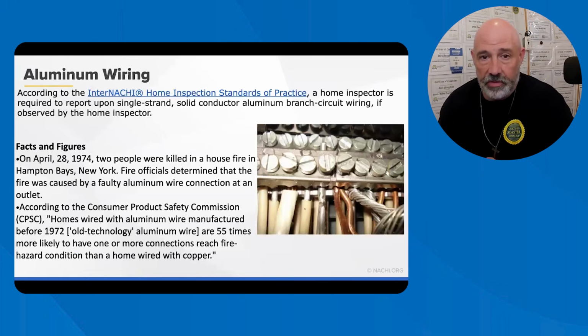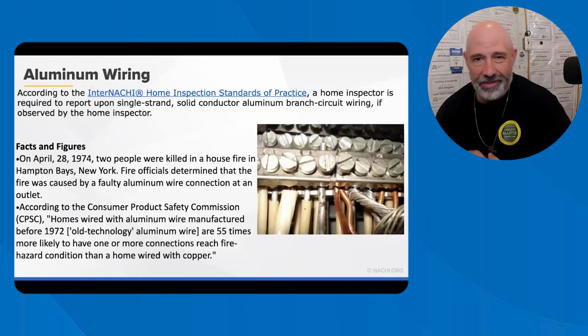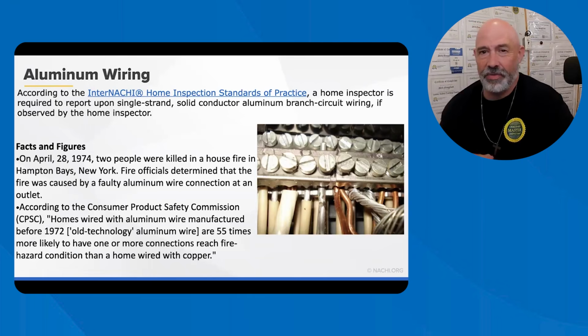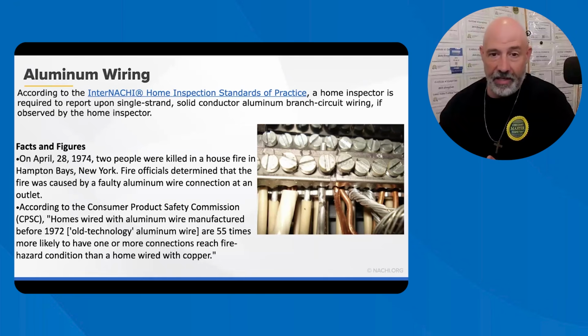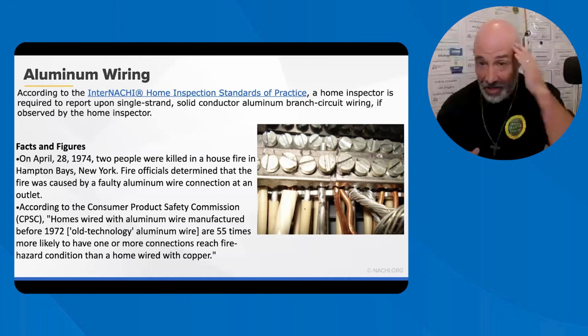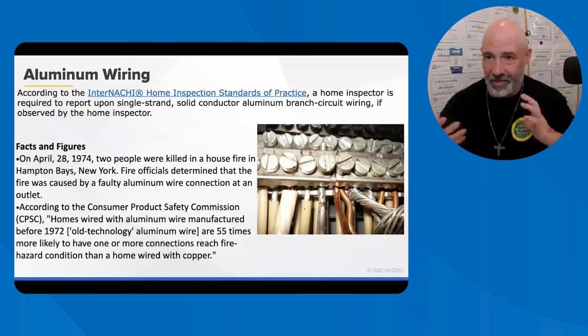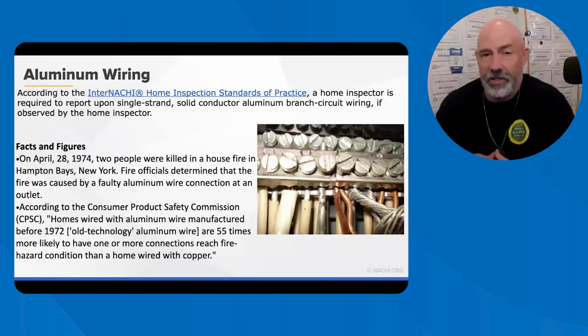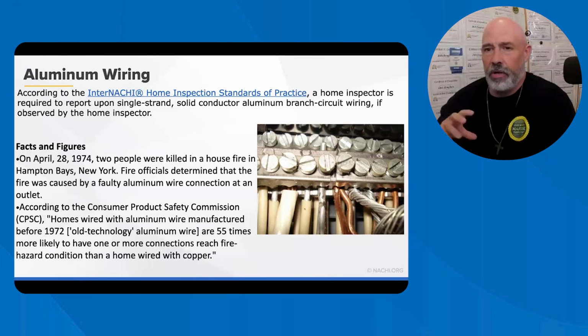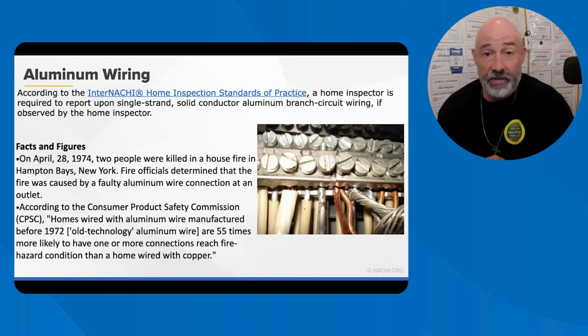Right around 1965, 1973, single-stranded aluminum wiring became really popular. I believe the copper price actually went skyrocketing those years, so they decided to use aluminum. Well, the problem with aluminum was that it didn't carry as much electricity long distances as the copper did, but a properly maintained aluminum system is acceptable in most areas. It's where the aluminum hits the copper, it's going to corrode. It's going to cause a major defect.